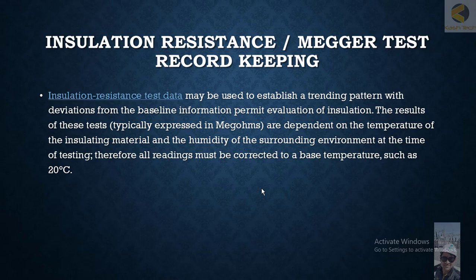Insulation resistance, Megger testing, and record keeping. When you are doing insulation resistance testing at the installation phase, you have to make a record and record the values.